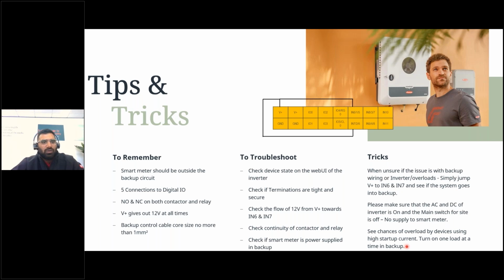So if you install the smart meter inside the backup wiring, what would happen is the system will go into backup. All of a sudden, the smart meter is power supplied. It will tell the inverter, I think the grid is back on again. So the system will shut down, trying to reconnect back to the grid. So it'll go in a loop, turning on and turning off in backup. So if you come across that scenario, please check if the smart meter is getting power supplied in the backup circuit.